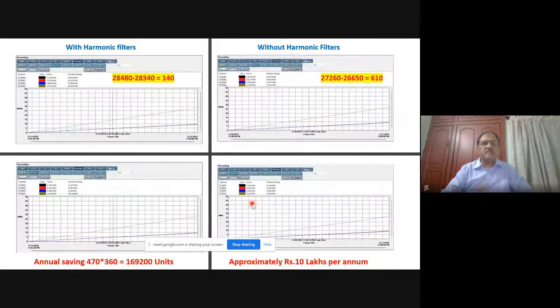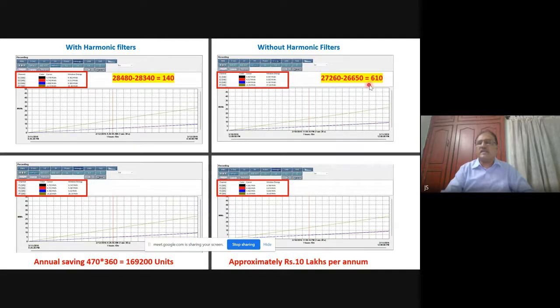When we did this exercise for the same customer, where we gave them almost 50 lakhs of saving from failed PCB components, we also found that there is a reduction in the difference between kVAH and kWH. If you notice here, I have put it in the red box. You will notice that from something like 610 units every day being the difference between kVAH and kWH, we brought it down to 140, thanks to the reduction in the total harmonic distortion current. You can make it 0. So the annual saving when we worked it out was 1,69,200 units, or approximately 10 lakh rupees per annum.